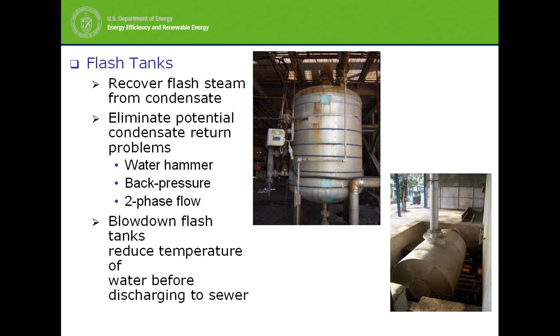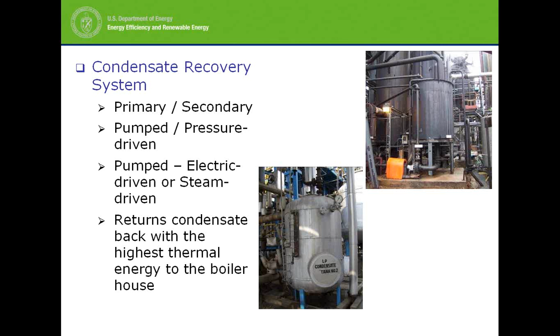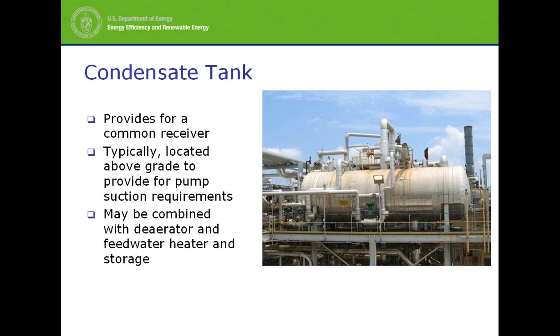Condensate recovery systems can be pumped - primary or secondary - with electric-driven pumps or steam-driven lift stations. Returning condensate back with the highest thermal energy to the boiler house is the key approach in evaluating condensate recovery systems: is condensate being collected, and if so, is it returned with the highest thermal energy possible? Condensate tanks could include a main condensate tank, or you could go directly into the deaerator depending on the system and its configuration.